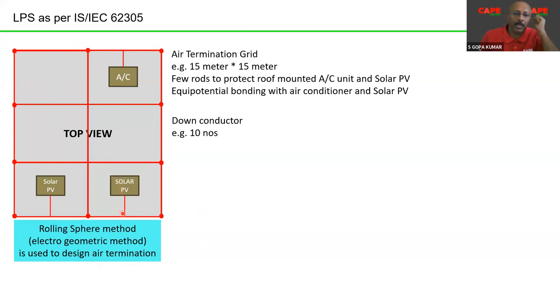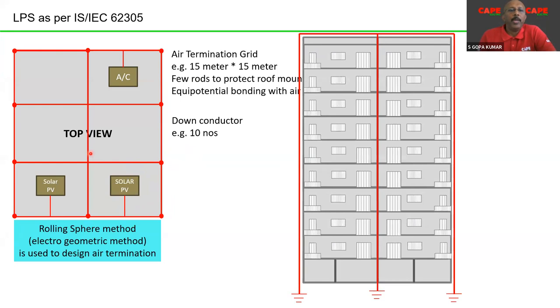The first point of the down conductor is the number of down conductors specified in the standard. Number two, if you require 10 down conductors, these must be placed outside the building, all around the periphery of the building. It has to be equidistant if possible, or the minimum distances mentioned in the standard must be maintained. Say, for example, maximum 10 meters, or an average of 10 meters, between down conductors. So in this typical case, we have, for example, 10 down conductors. You can see the building at the top, there is a mesh and there are 10 down conductors, and each of the down conductors has to be connected to an earth termination system.